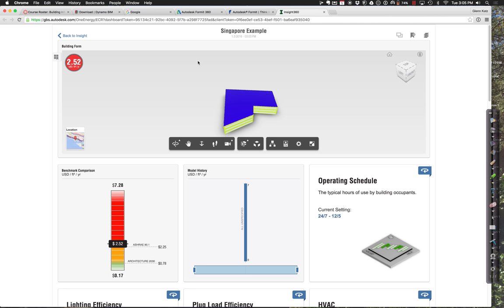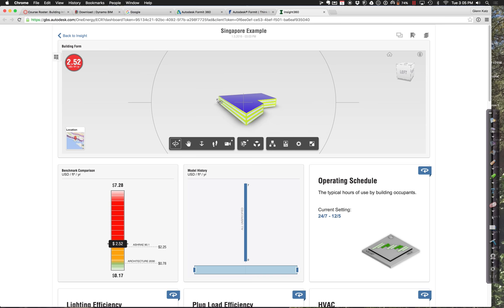Here's our basic little building, and you can see just based on the data we've put in so far it's indicating what the window-to-wall ratios are and what the different surfaces are. Right now it's estimating 2.52 dollars per square foot per year, which is actually not too awfully bad — a little bit higher than the ASHRAE standard. There's a range of values — from the worst assumptions, the least conservative and most energy-wasting, all the way to the absolute best performance. The idea is to figure out how to get better performance in the most meaningful way.